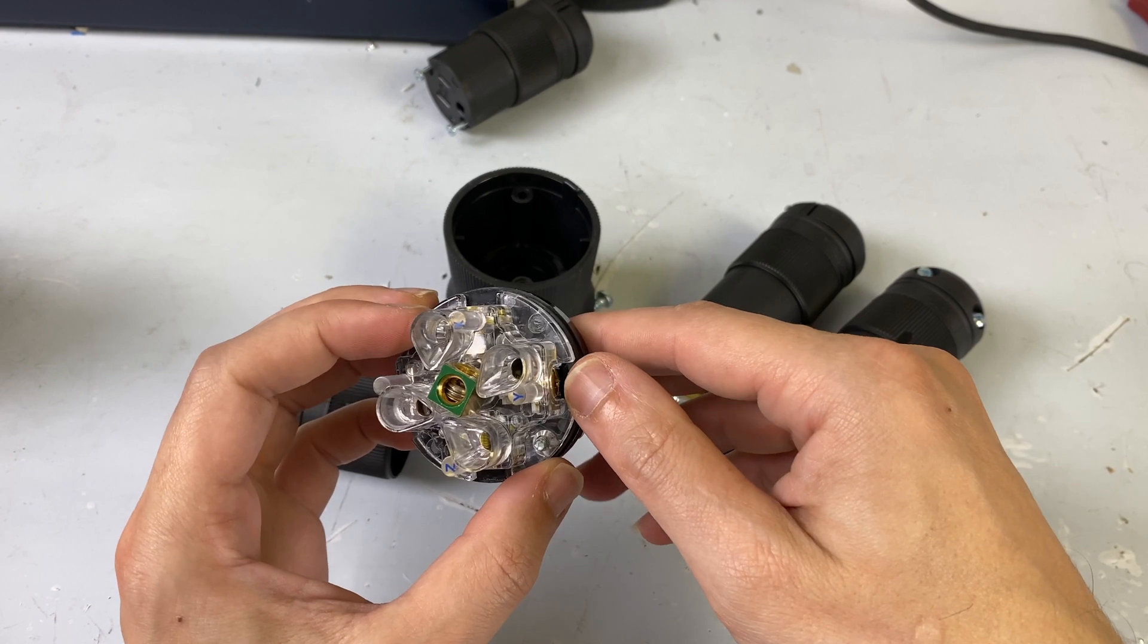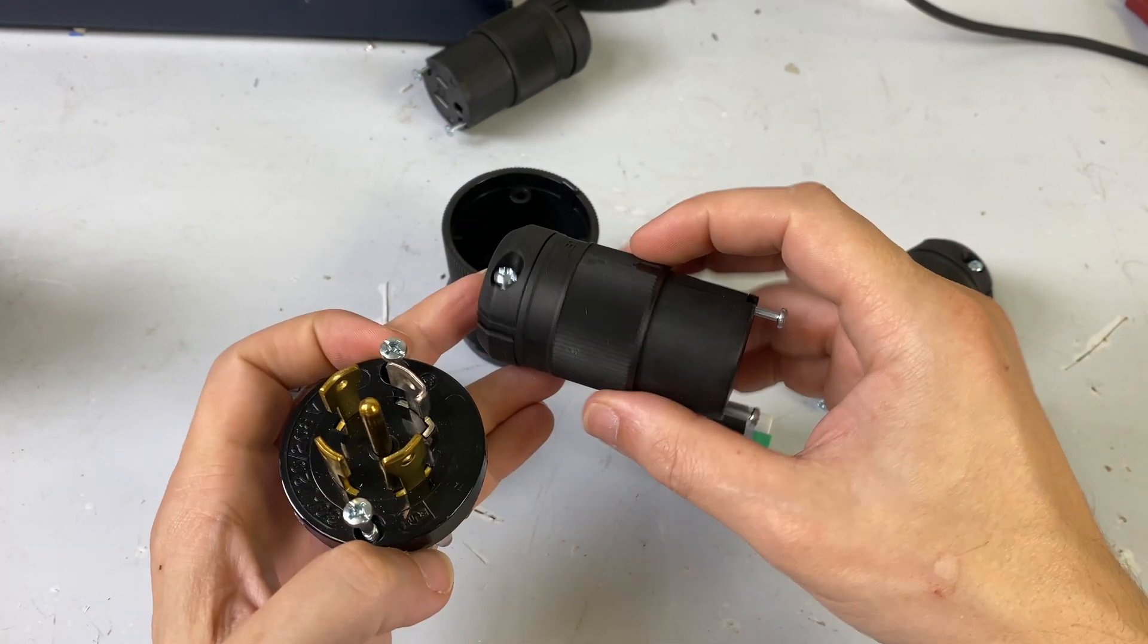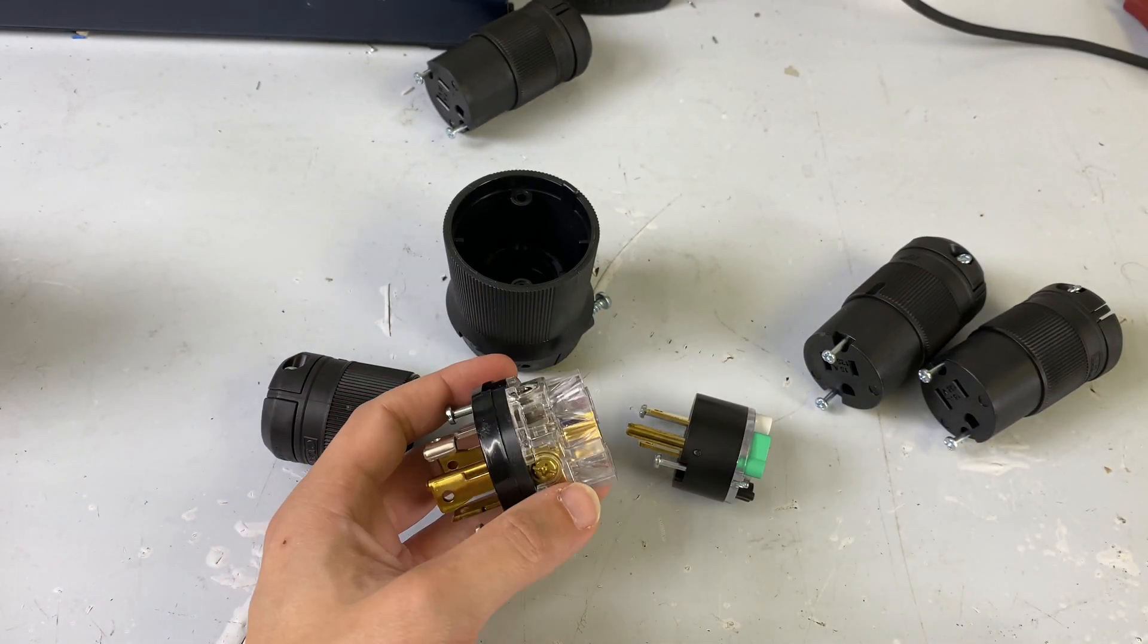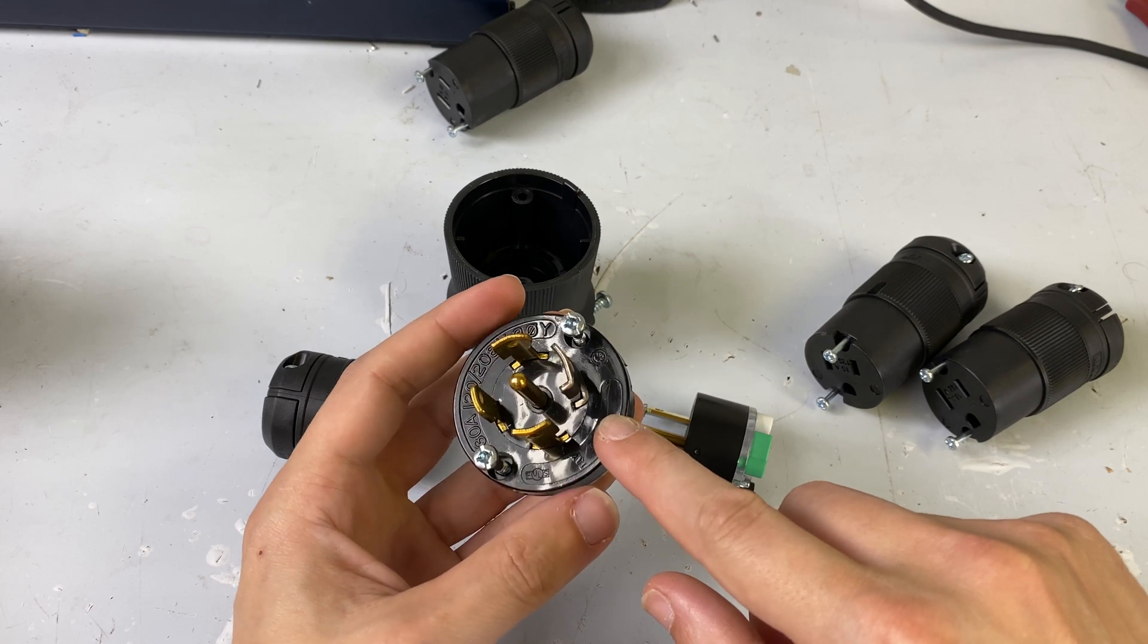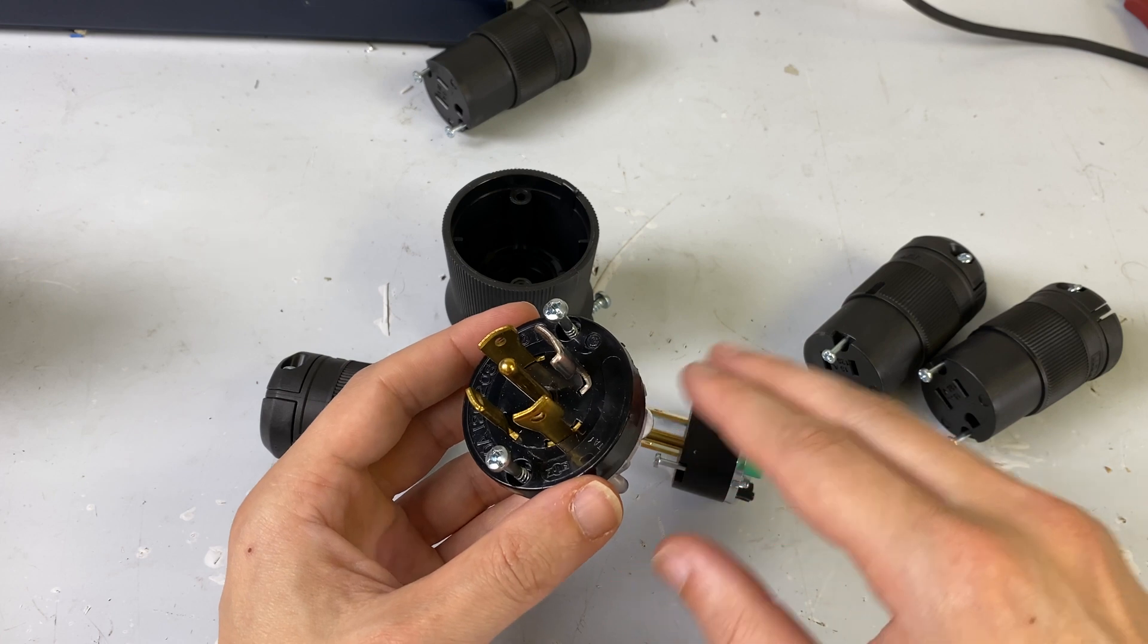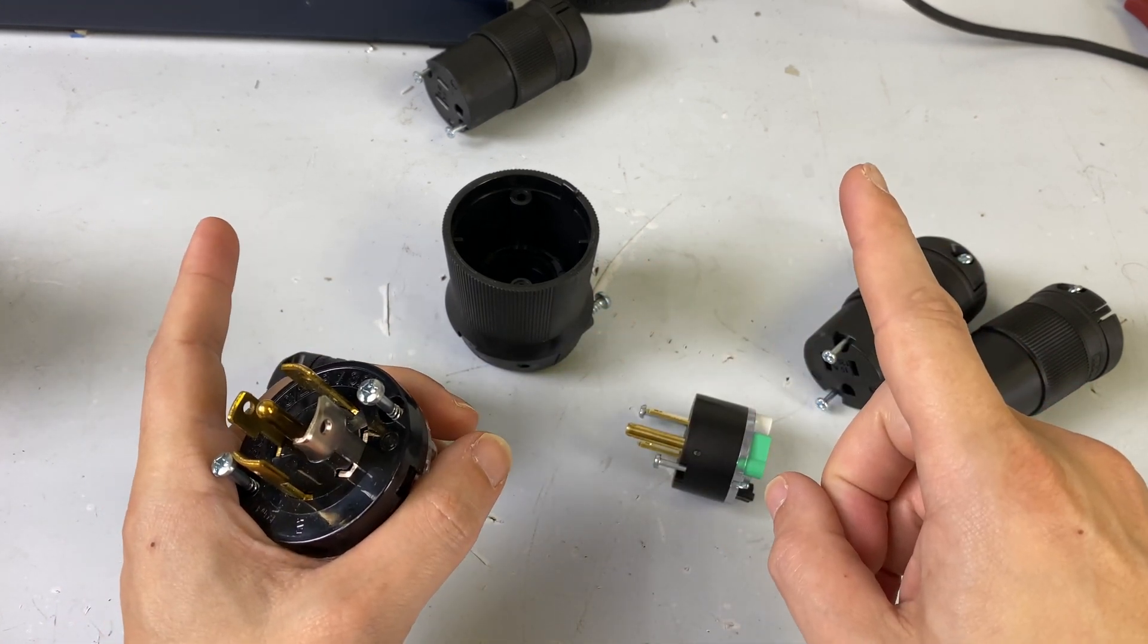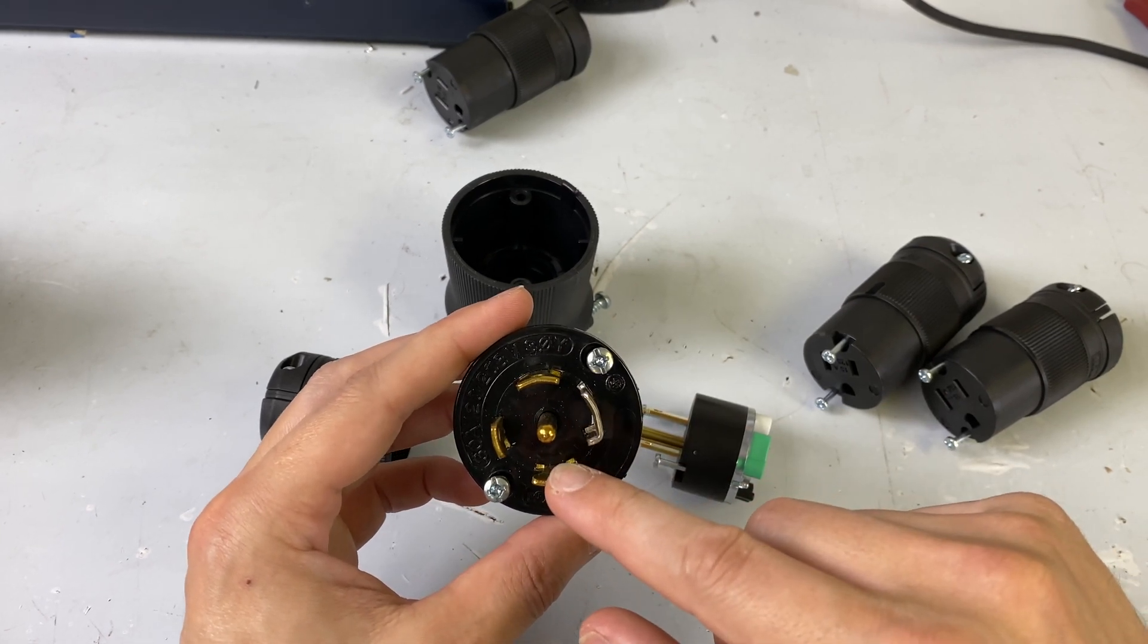So what we're going to do today with our cable is we're going to take each one of these hots and isolate it to a single one of just a standard 15-amp Edison. We're calling it Edison because that's an audiovisual term for this. You might ask, why would you want this? Well, on a common distro that gives you a bunch of different output options, we can run one cable line, which we would call a trunk line, down to wherever we need power, and then break that out into individual outputs, three separate individual outputs on one cable. You're carrying three individual outputs on one connector.